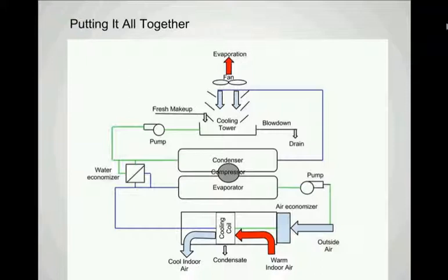That water passes through the heat exchanger of the condenser. The water is pumped up to the cooling tower, as we've seen, and flows through the cooling tower. By evaporative cooling and sensible heat removal, with the fan pulling the cold air through the water flow, a portion of that water evaporates to cool it so it can be recycled back through the condenser where it picks up more heat.